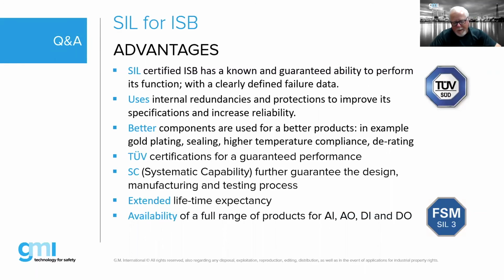Okay, our SIL rating. Basically, what we're trying to do here is we now have defined failures, if you will. We know how reliable our product is going to be since we've independently tested it and verified it by a third party. So again, you've got defined failure data. What this really means to me, again, is not a requirement by any stretch unless you're using barriers in a SIL loop or something like that. But just to use a SIL rated product, really all it means is that the product has been certified, that you know the failure rate and that it's going to be extremely reliable. That's really what you're getting by buying a product that actually has a SIL rating.